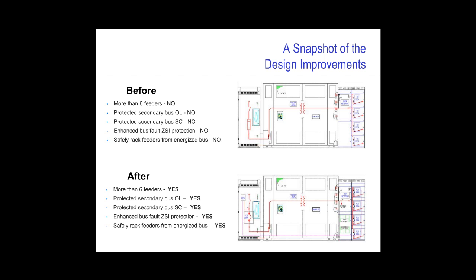And finally, because I've added secondary bus protection, I can more safely rack feeder breakers from an energized bus, knowing that in the event of a fault, I'll clear the upstream device, the vacuum circuit breaker, much faster. This allows operators to reduce the amount of PPE that's required during maintenance of this equipment.